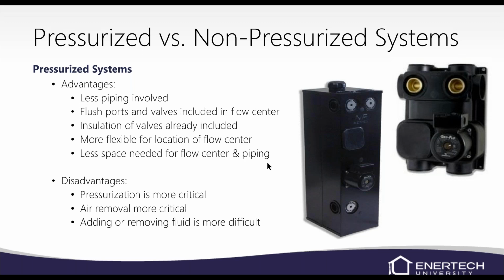Either one of these flow centers or loop field, you're going to have to flush with a flush cart. The pumps on the flow centers are not big enough to flush all the air out. And regardless of whether it's pressurized or non-pressurized, you still have to flush the loop field on initial startup. There's a little bit of air in the system. It will work its way back in a non-pressurized and float to the top of this tank, and then escape through that cap on the top. But that's just micro bubbles or something, not big air pockets.